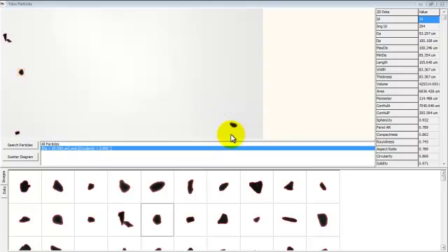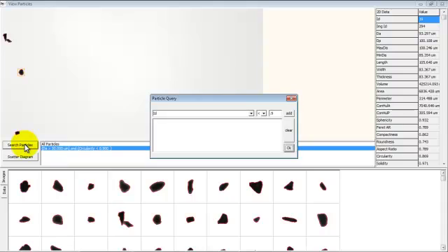Out of focus particles would corrupt the accuracy of the results. The Search Particles tab here can be used to filter the particles into groups that meet certain parameter restrictions. For example, here we're displaying only images that have equivalent diameters greater than 50 microns and circularities less than 0.9.